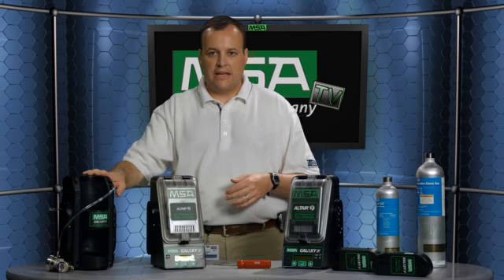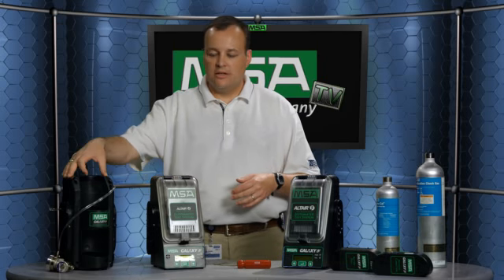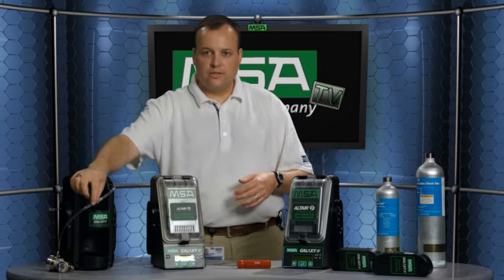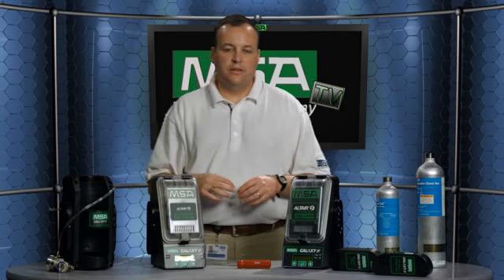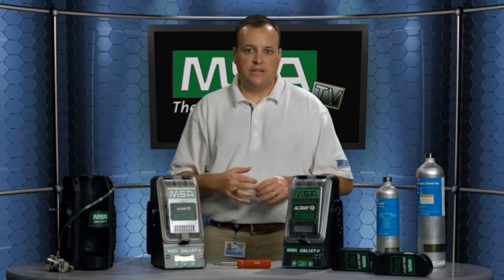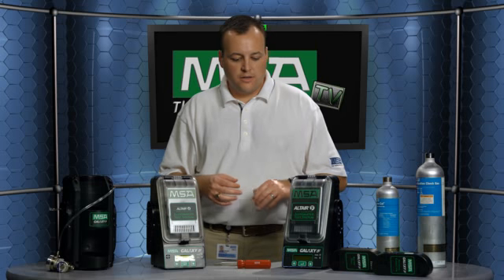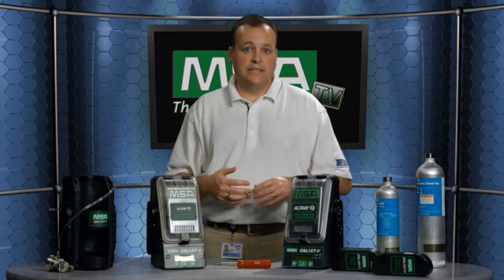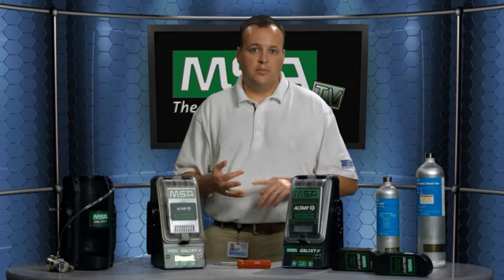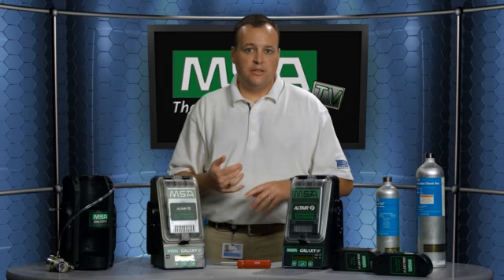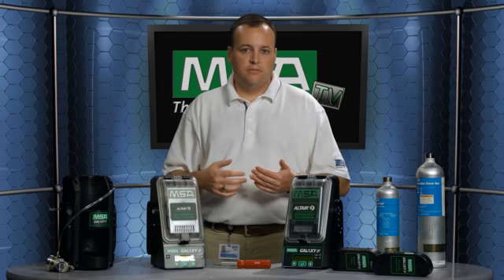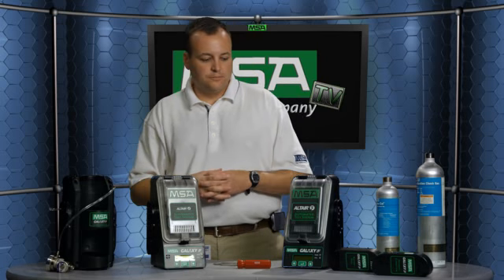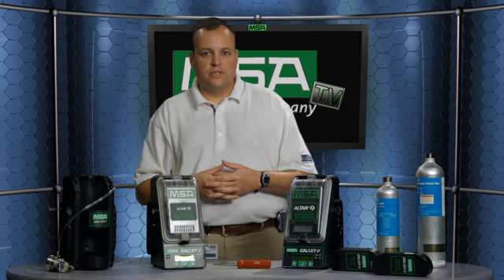You would then plug in your test stands. You would hook up your gas cylinders of choice into the gas cylinder holder. Gas cylinder holder comes supplied with a demand flow regulator, which is very convenient again for you. In plugging them in, you'll basically need to set the date and the time and the gas type, and then some other really brief things that you'd have to do, and you'll be ready to use this instrument in a short amount of time. So it's very easy to use and set up.